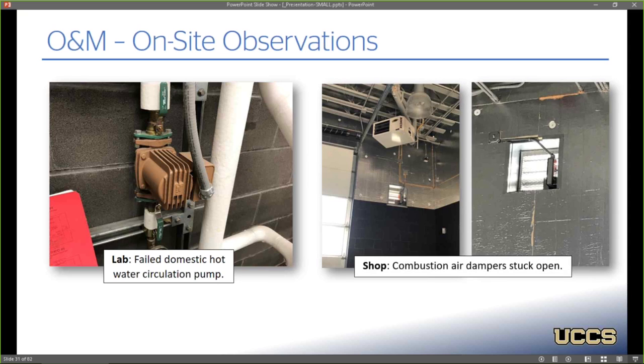The shop unit heaters are wired to a couple outside air dampers that are supposed to open for combustion air to enter the space when those units are enabled. But those dampers are just stuck open, which means in the winter months it's going to be hemorrhaging heat just constantly.